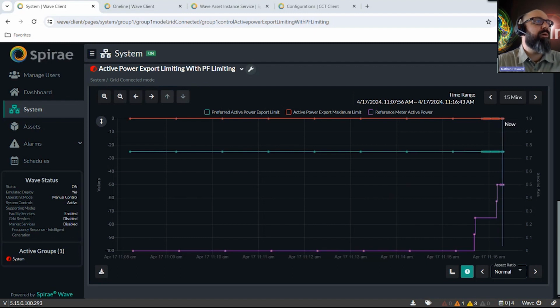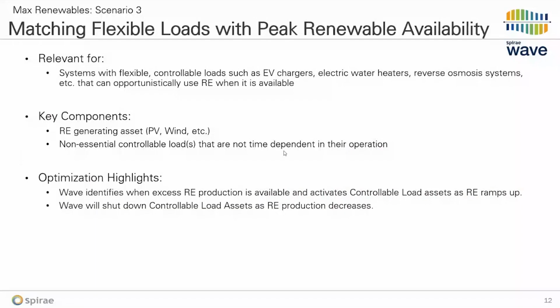And so we'll see that as that available production comes up, we'll start heading towards that limit. But again, because we want to make sure we're meeting those requirements from the utility, we're actually going to curtail the PV production in the system so that we stay a nice margin below that limit, with no danger of violating it. So we'll use as much as we can to meet our load, but we're also going to make sure that we're not violating that limit here. So we'll curtail that production. So obviously, curtailing our renewable energy production is not ideal. Where we can, we want to make best use of that. This whole presentation is about maximizing your renewables.